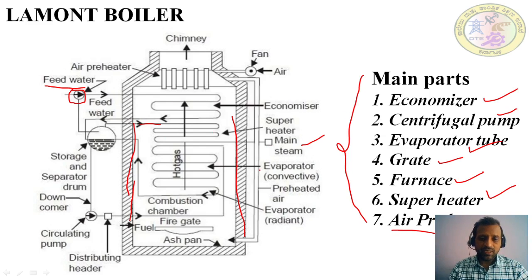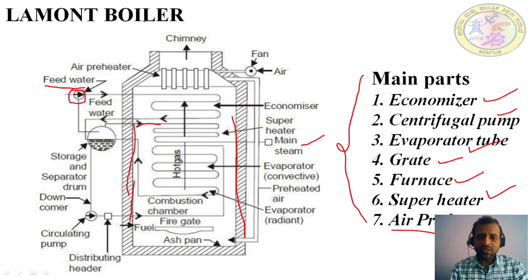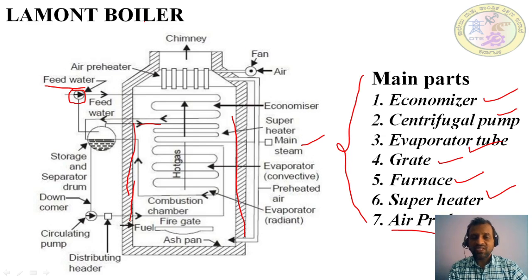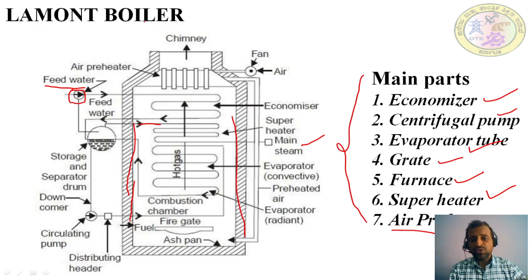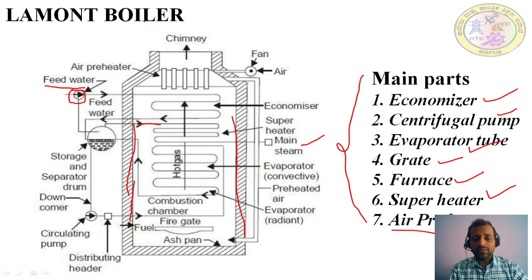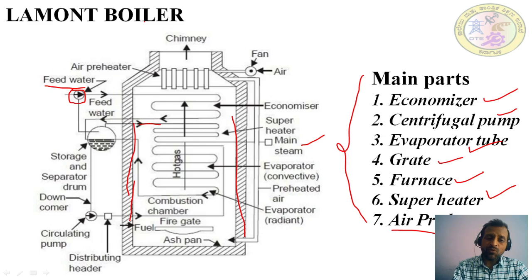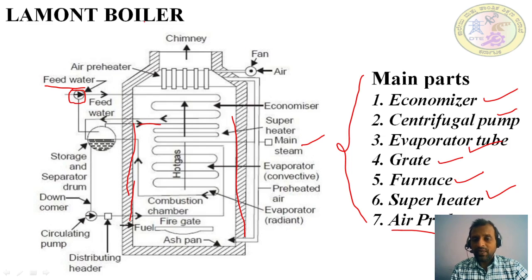This is the working of the Lamont boiler. The key concept to understand is that in low pressure boilers, water enters naturally — natural convection takes place. But in high pressure boilers, water is forced using a pump — forced circulation. Whenever you use the pump, it sends water at high pressure into the boiler. This is the very important difference between low pressure and high pressure boilers.